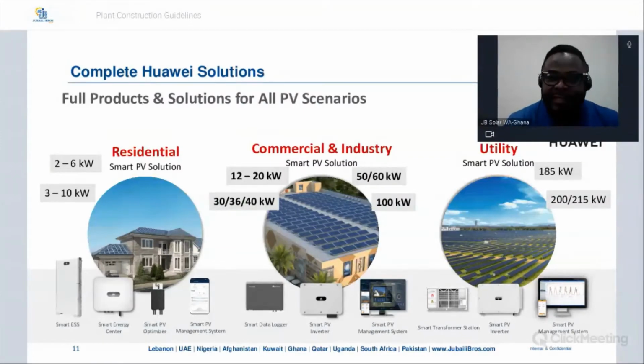And then we have the biggest C&I inverter in the system. One of my absolute favorites, I've always said, is the 100 kilowatt inverter, 10 MPPTs. Each MPPT has 2 strings, which makes it have 20 inputs in all. You don't need a DC combiner box. You just terminate all the DC strings directly onto the inverter. That is absolutely magic. That's the 100 kilowatts that we have here.